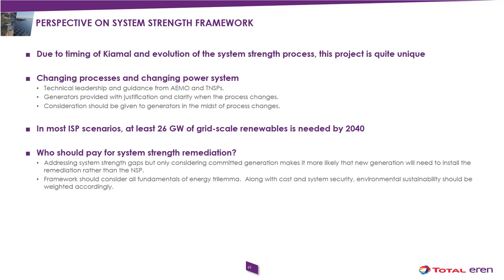Now, I find that the issue at present with the system strength framework is that it's a little skewed. If we just pause and think, if you have a system that doesn't have much fat, as I think it's clear that the system doesn't, and every time you bring on new generation, if that generation is going to cause an adverse system strength impact, then it's going to be the generator who has to pay and install that remediation rather than the NSP.